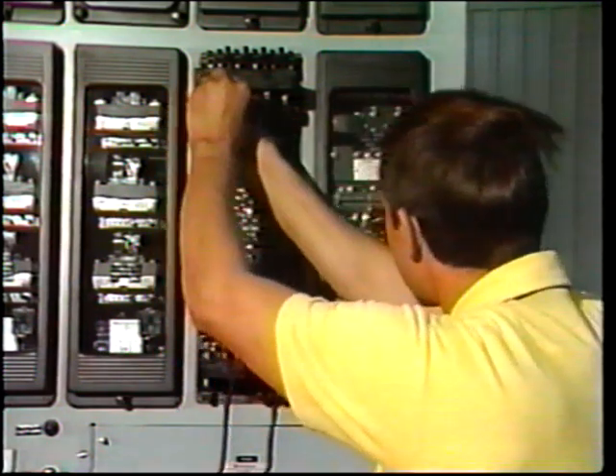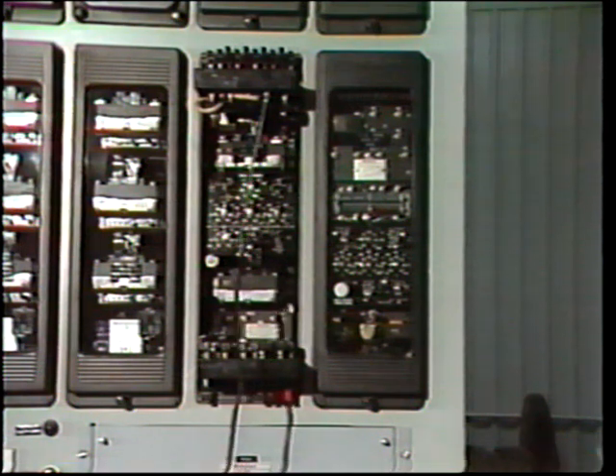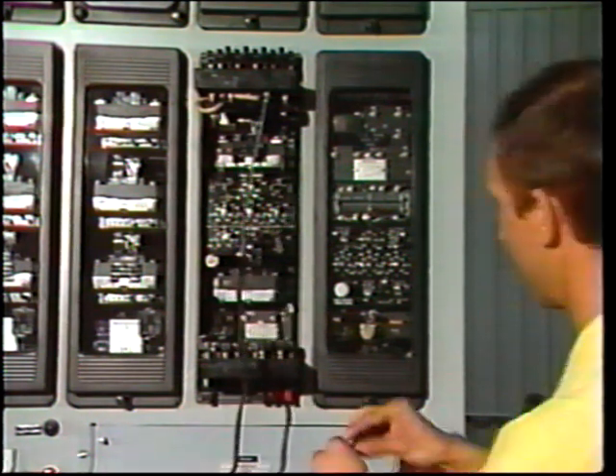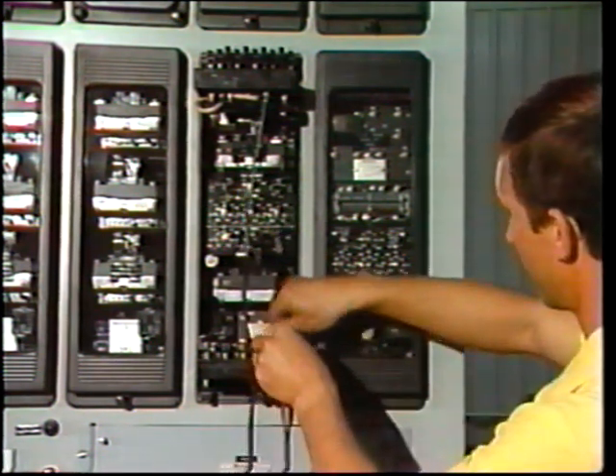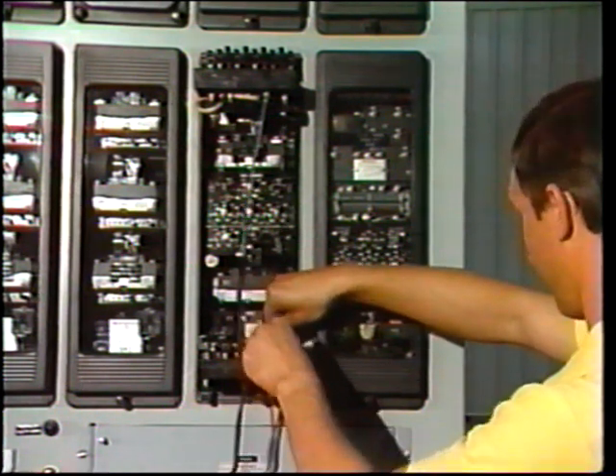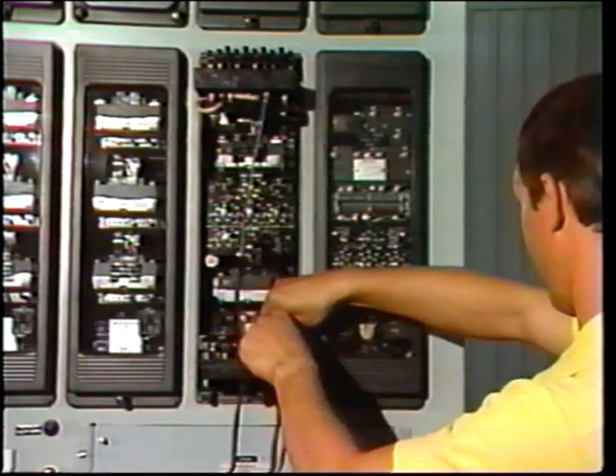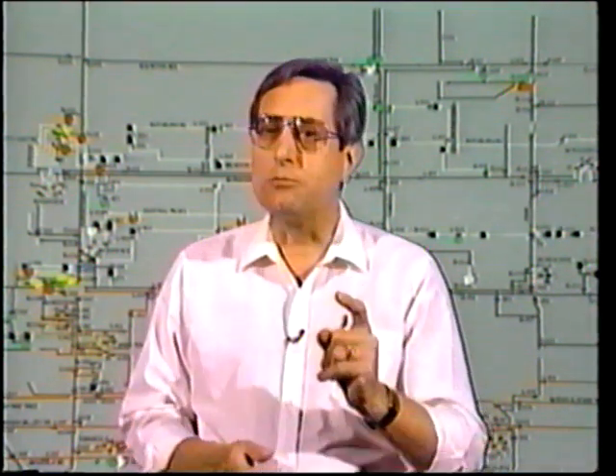Now we're coming to the real nitty-gritty. The potential for inadvertent tripping under these conditions is quite high. One false move by the relay technician and he will trip out the very line that he is trying to keep in service. It is ironic that by performing the tests to ensure that protection equipment will not cause incorrect tripping, we run the possible risk of inadvertent tripping during the very test itself.